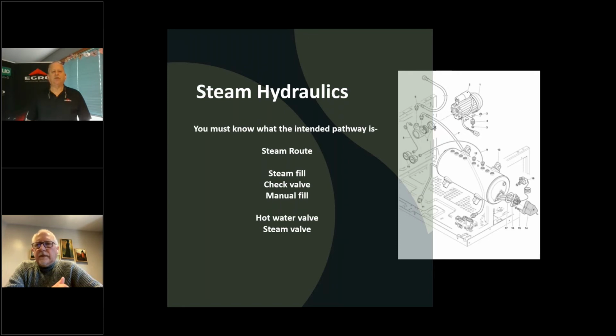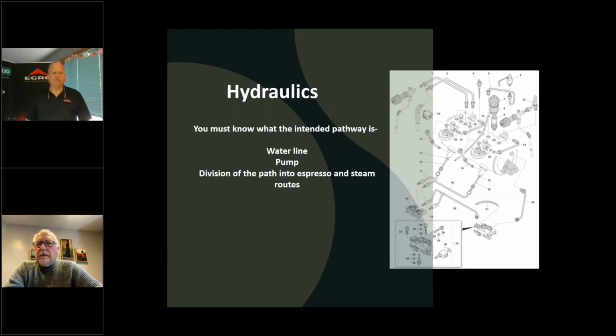By the way, one thing I should mention, stepping back to the previous slide, the water line. I venture to say that half of the technicians out there touching a Rancilio don't realize that in the end of the water line is a check valve and a little strainer. And once again, back to how we designed the machine, and all of those little pitfalls throughout the machine where there could be an issue. Now, it's only been an issue about 10 times, because somebody didn't flush a water filter in one region of the country for one technician. Nobody else has registered it. It's good to know. You pull the water line off, and you've got water there. I plug it in, the machine has water. No, it doesn't, because you lost it right at the check valve. But anyway, let's go ahead and go forward, please.